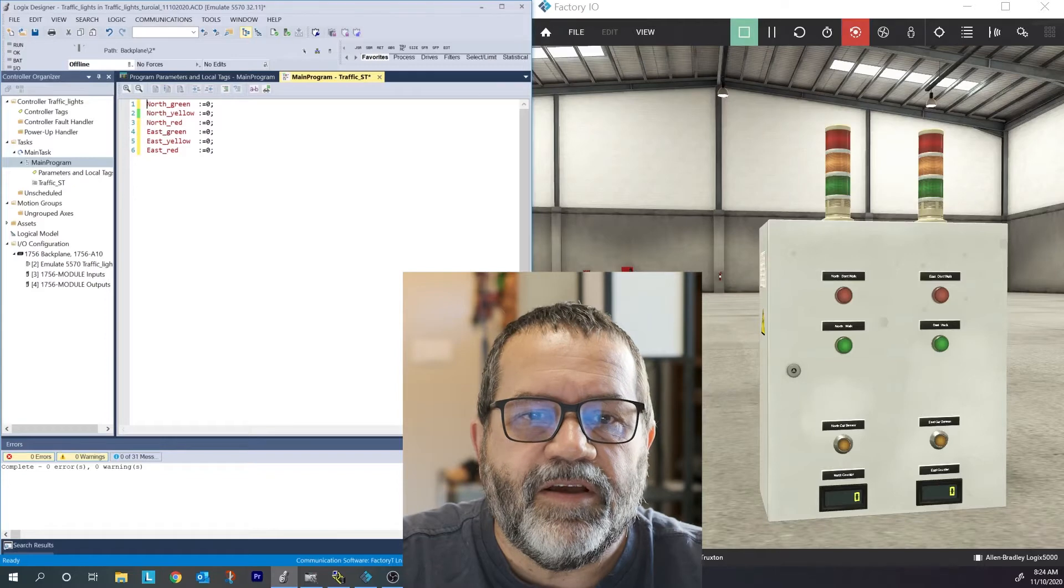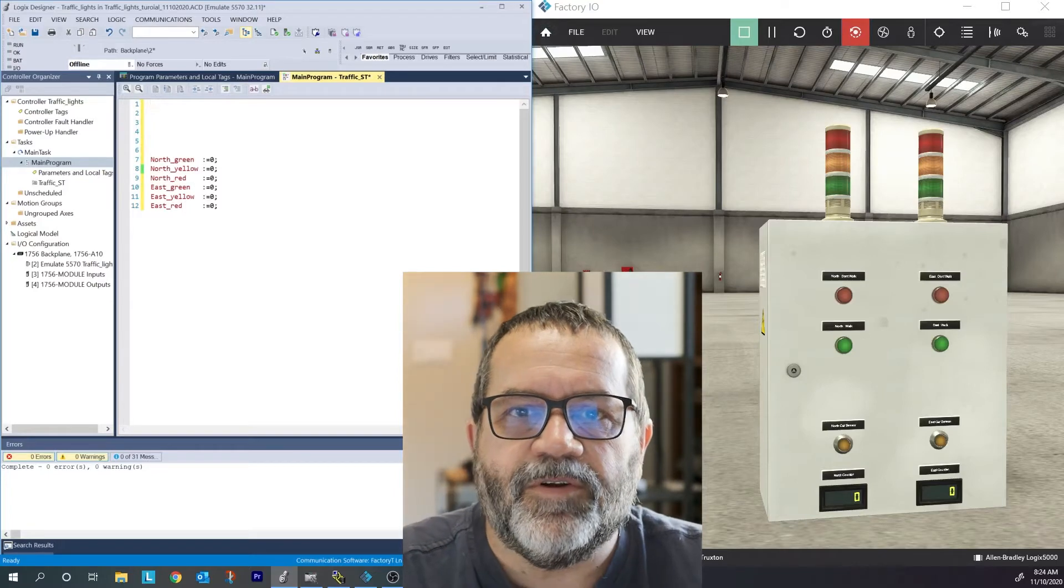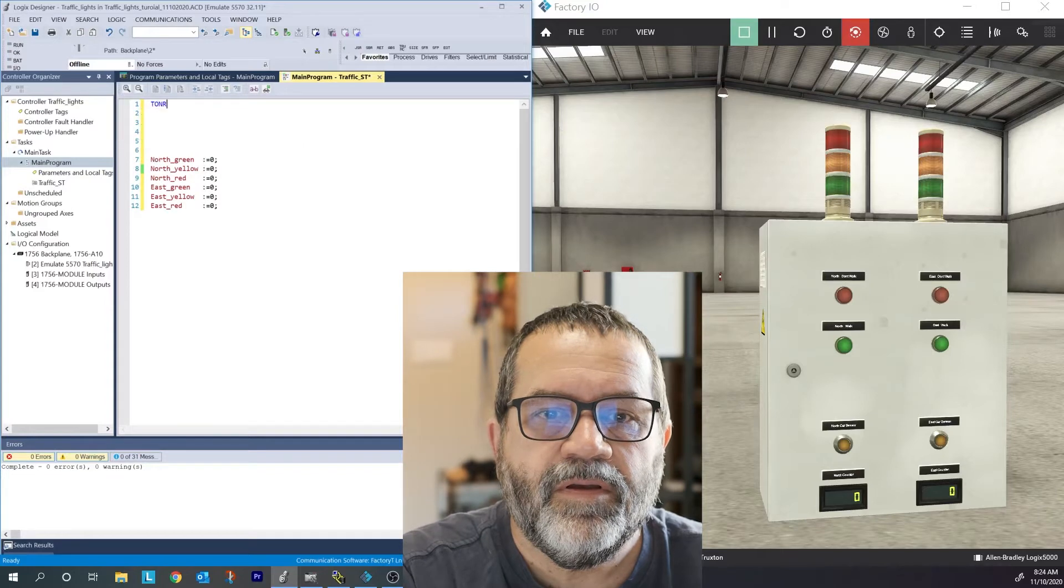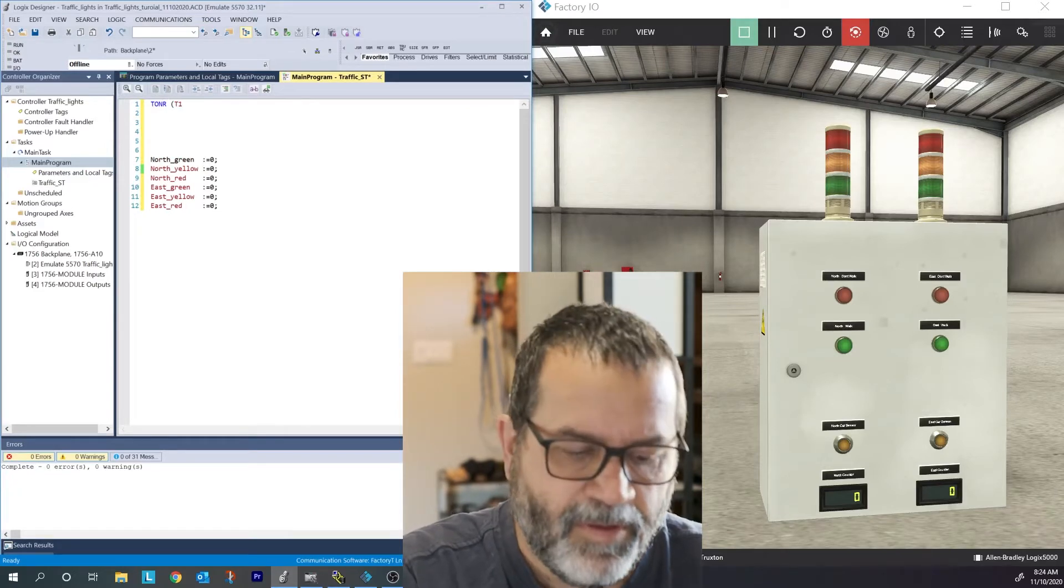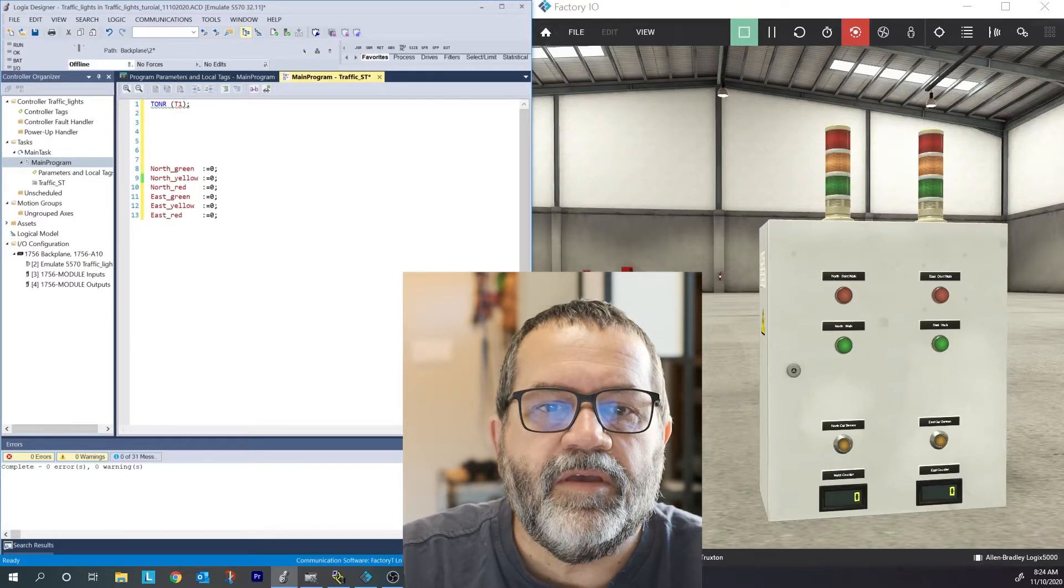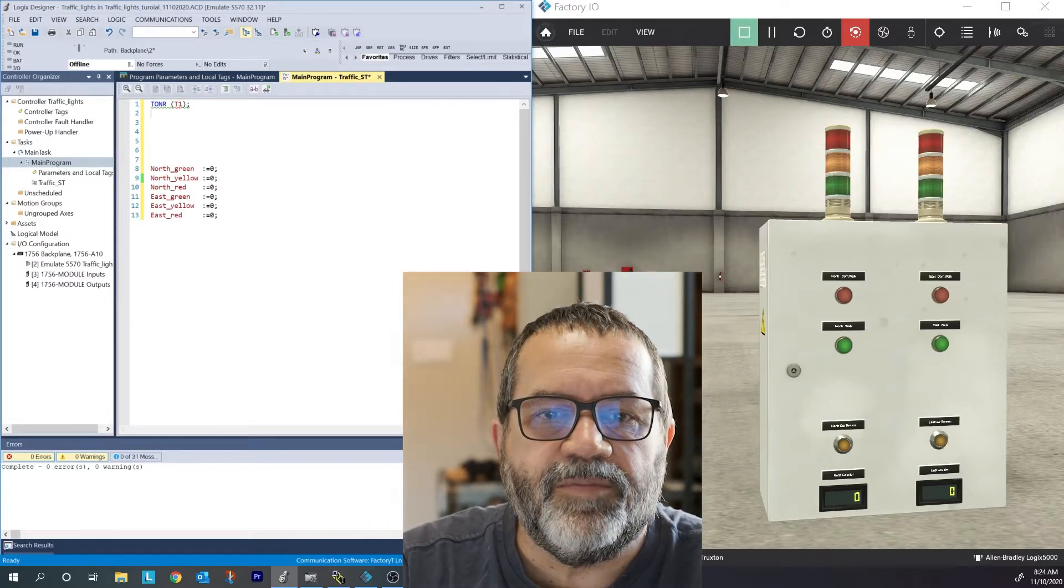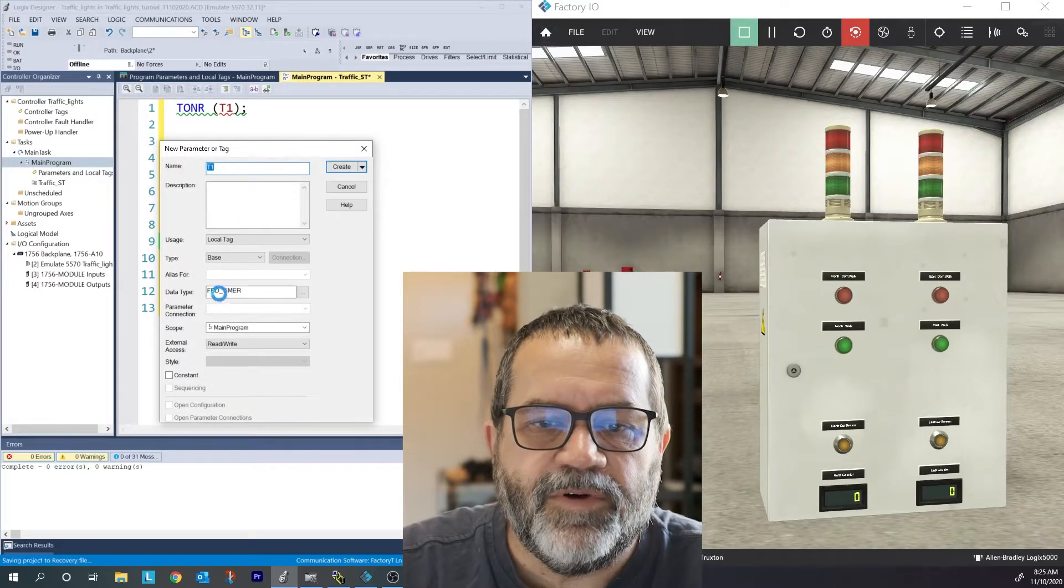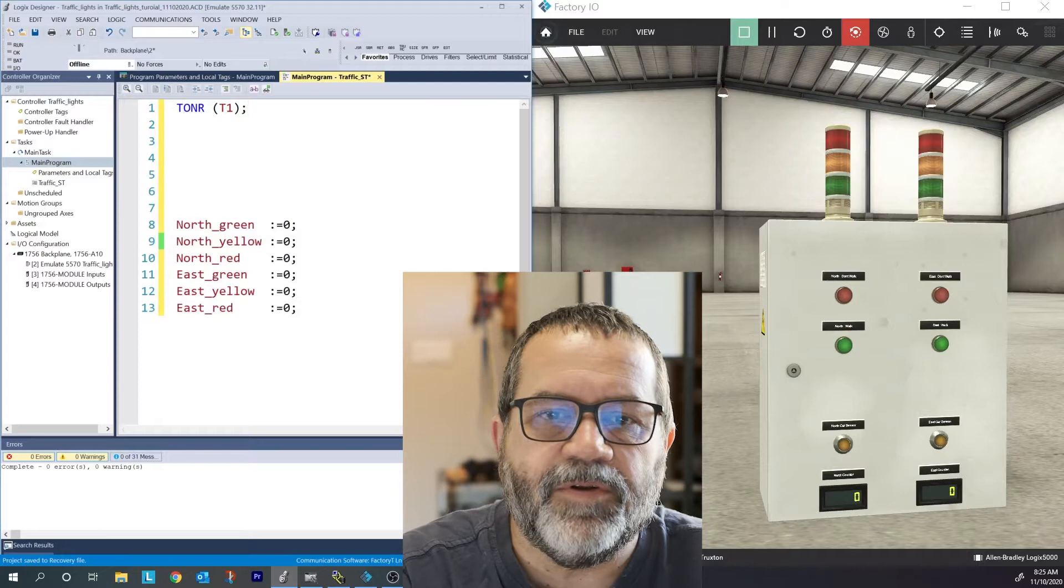Before I get to that, I need a timer. So let me space this down a bit. And I'm only going to use one timer in this. So I'll start with TONR and I'm going to call that, I'll just call it T1. And now when I do that, I've got some errors already. I have the little red squiggly under my T1. I'll right click on that and it says, do you want to make a new tag? Sure. And it knows I want an FBD timer. So I'll create that. There's my T1 timer.